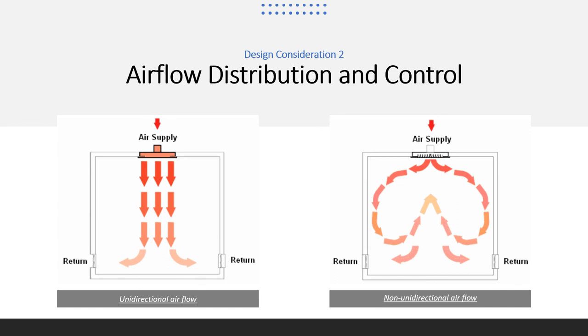The flow of air in a downflow clean room bathes the room in a downward flow of clean air. Contamination generated in the room is generally swept down and out through the return. The horizontal flow clean room uses the same filtration airflow technique as the downflow, except the air flows across the room from the supply wall to the return wall. Between the two, the vertical downflow pattern yields better results and is more adaptable to pharmaceutical production.